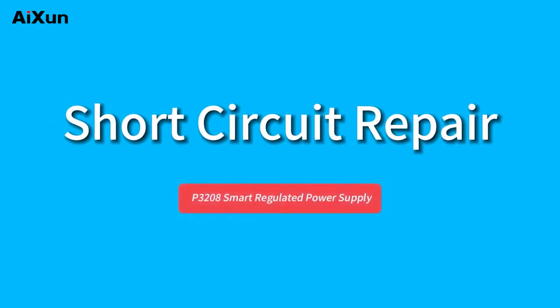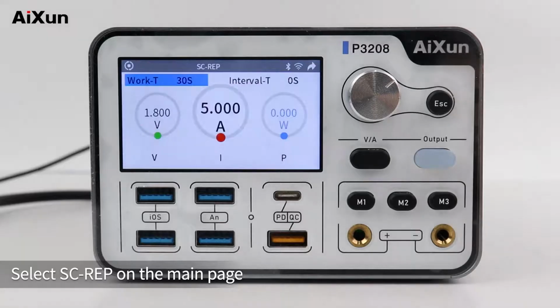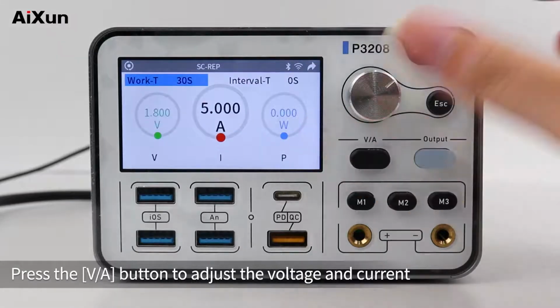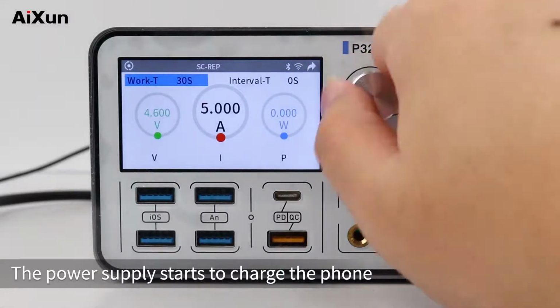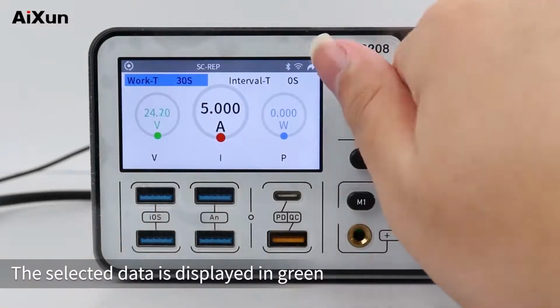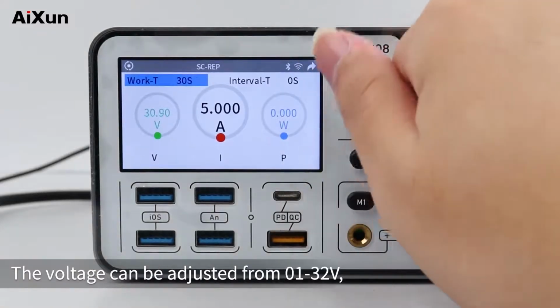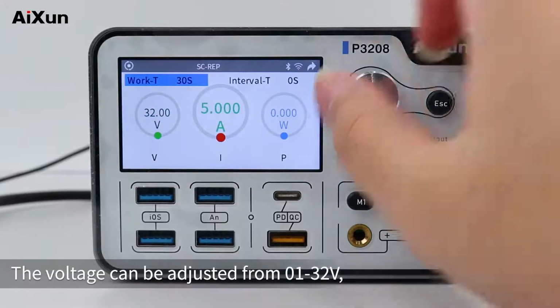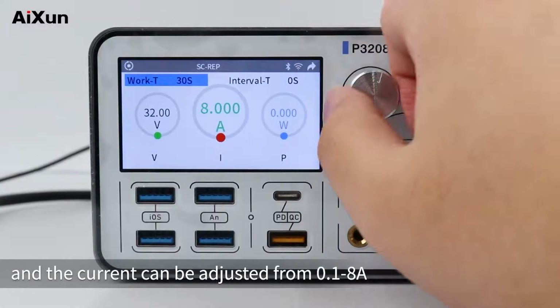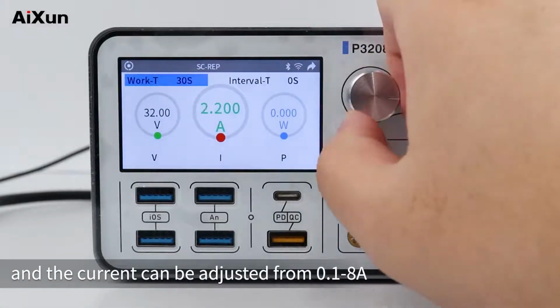Short circuit repair. Select short circuit repair on the main page. Press the V/A button to adjust the voltage and current. The selected data is displayed in green. The voltage can be adjusted from 0.1-32 V and the current can be adjusted from 0.1-8 A.